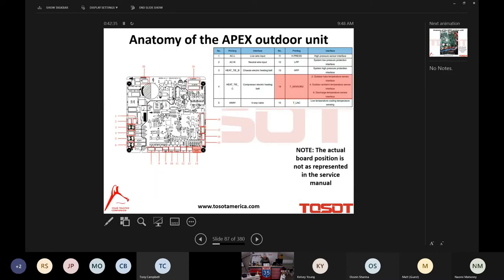I hope so. And then we have our sensors, our thermistors, I should say. There's a total of four thermistors. A thermistor, people, being nothing more than an electronic temperature sensor. Virtually all thermostats nowadays are working on an electronic thermistor as opposed to an old mercury bulb thermostat like a Honeywell T87F. And that's what these are. These are temperature sensing thermistors. There's four of them. We have the outdoor temperature sensor. We have the outdoor tube, which is essentially the heat exchanger temperature sensor. And we have a discharge temperature sensor. And that is the discharge of the refrigerant coming off the top of the compressor. And I'll show you each of them.